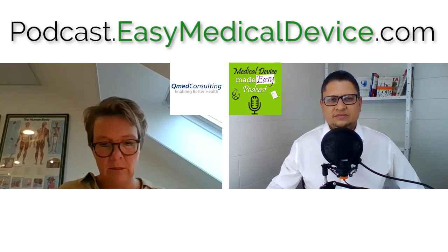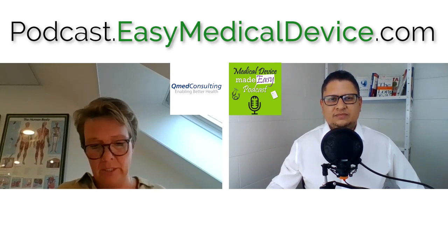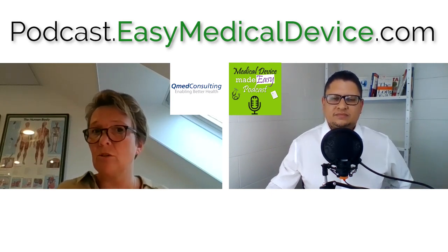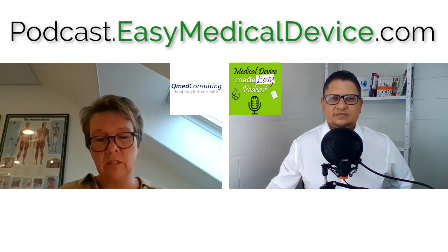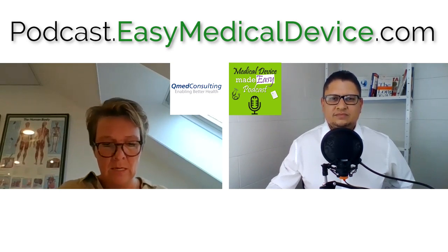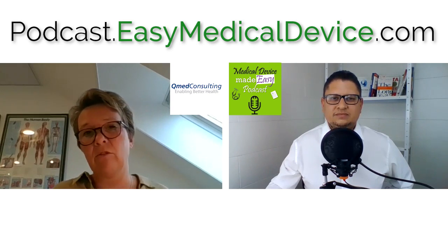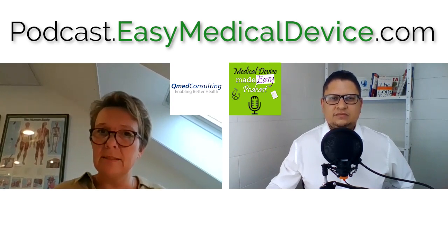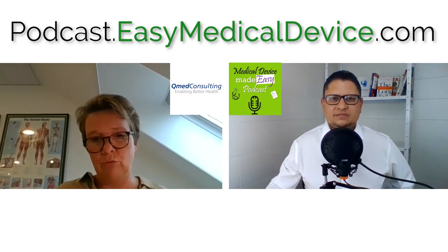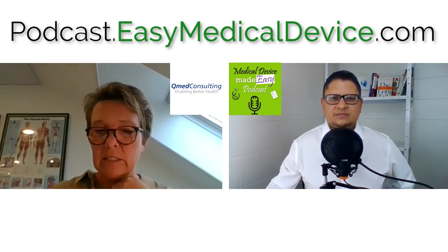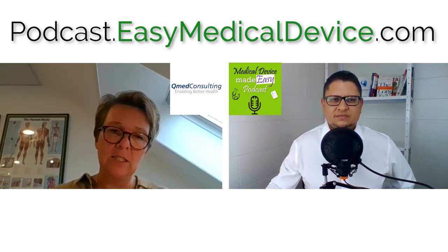So if you look at clinical evidence, it must be the same clinical condition or purpose, and also similar severity and state of disease, for instance. So very specific and very precise. Used in the same side of the body, used in a similar population, so in regards to age and gender and anatomy and physiology. Same kind of user and same kind of critical performance. So if you can fulfill that, then you are able to demonstrate clinical equivalence. The same for biological and technical equivalence.